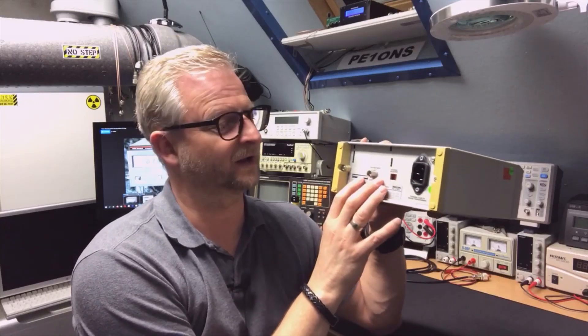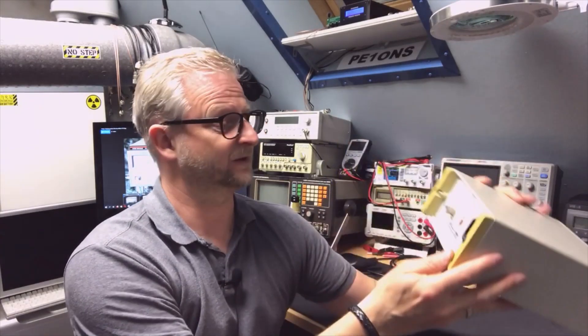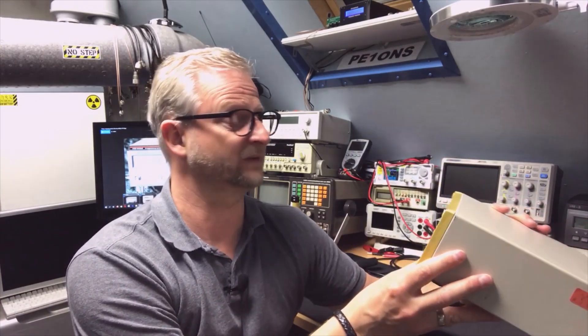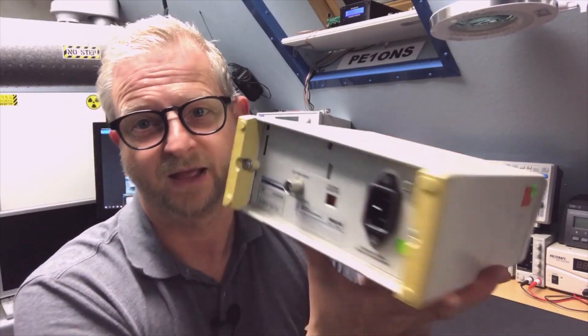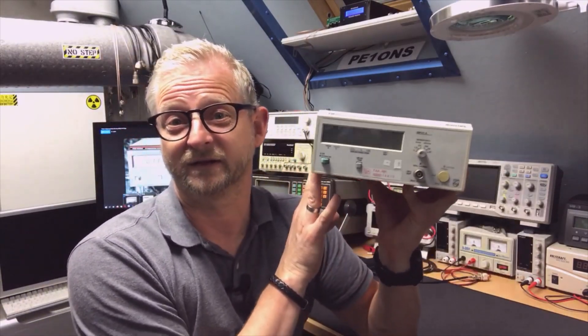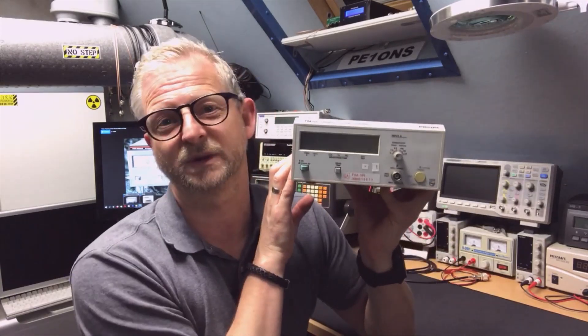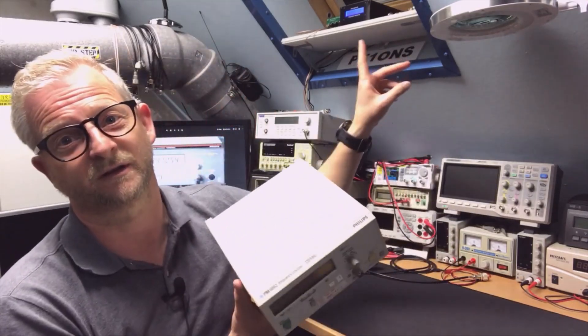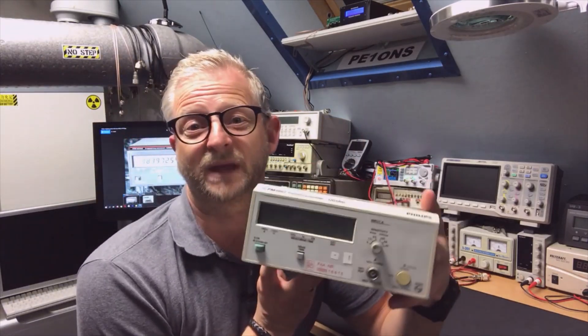Unlike cheaper models, it has an external reference input for 10 MHz that accepts 0.5 to 15 volts RMS. This increases accuracy because the internal time base doesn't have to be that precise. We can connect it to our lab reference, which makes it very nice.